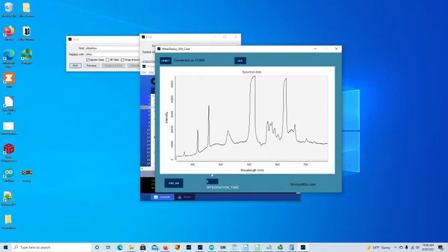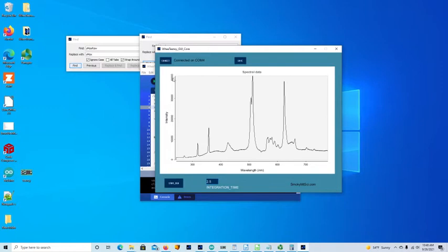So let's back that down, and I believe 2.5 is what we're looking for. I should also say that the maximum number that your A to D converter will give you is about 65,000. So at 50,000, yeah, we're probably maxing out the intensity. We're saturating our detector. All right, so at 2.5 milliseconds integration time, we have a little over 40,000 counts, and that looks pretty good.